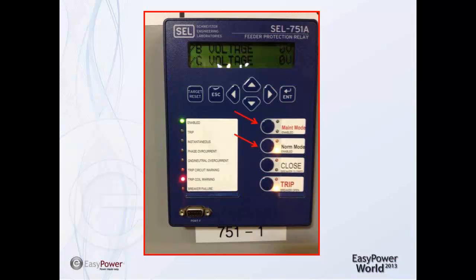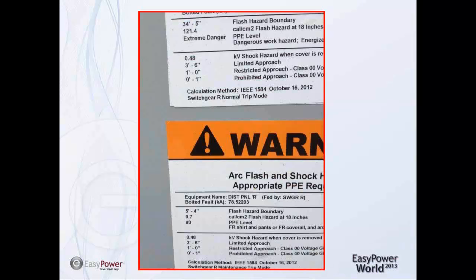One of the things we really rely on EasyPower for is the ability to know what our incident energy is in a particular location when we're in maintenance mode. This is a really big deal for us because we do a lot of breaker interaction and a lot of switching. We have to rack breakers in and out of equipment quite often, especially on down days.